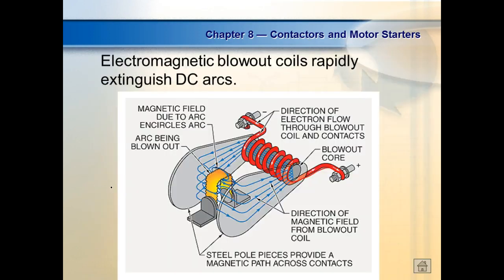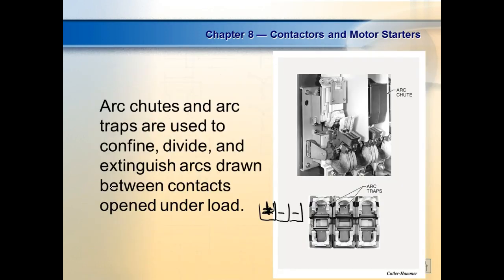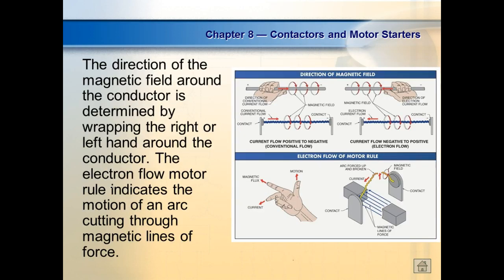So these are your newer motor starters. The contactors that I used to have, these relay contacts were all exposed, right? So they've changed a lot since the NFPA 70E came out. And what we do with big high-powered DC arcs is we blow them out with a magnetic field. So this is one way we can figure it out.